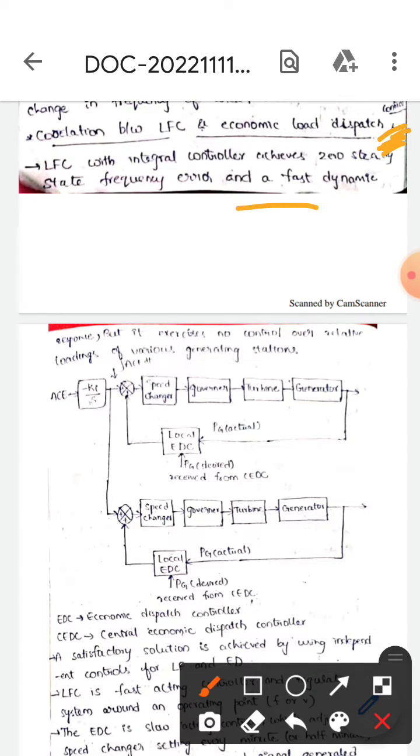Here LFC means load frequency control. LFC with integrated control achieves zero steady state frequency error and a fast dynamic response, but it exercises no control over relative loadings of various generating stations.